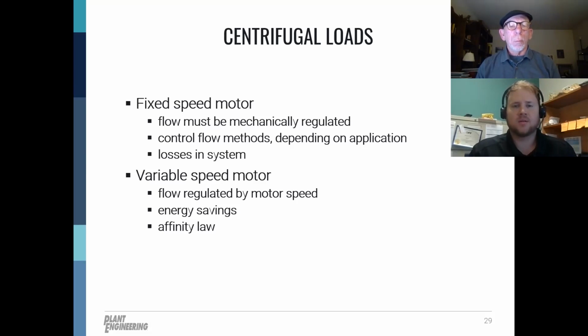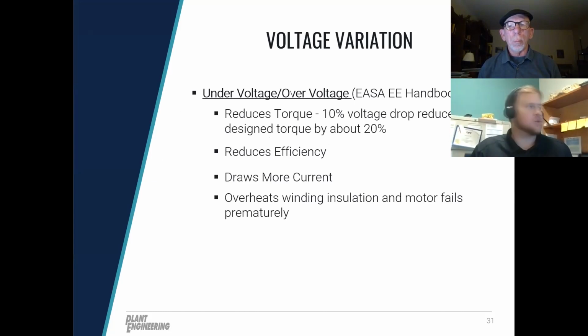So in most cases, there are types of motors where you may be able to do this without a control, without a variable frequency drive, but it's most common today to have a variable frequency drive to control the variable speed motor. And VFDs can be beneficial in a lot of cases, but one thing I have been seeing recently is a lot of clients having some issues with VFDs and power quality events. And that's why I wanted to work some power quality discussion into this training today, because VFDs and controllers can be very sensitive to power quality issues. First thing we're going to talk about is some power quality basics. And then we'll go over a few power quality solutions.